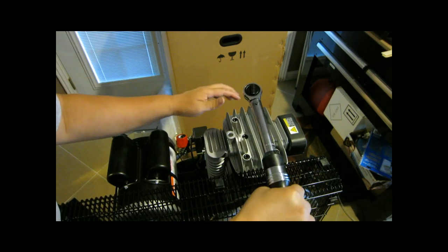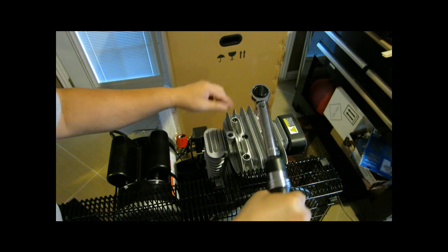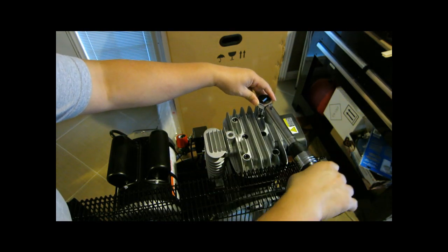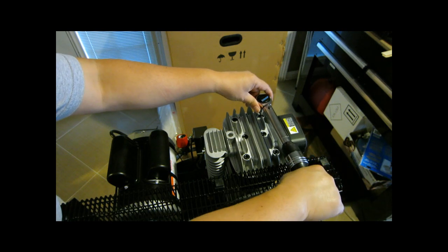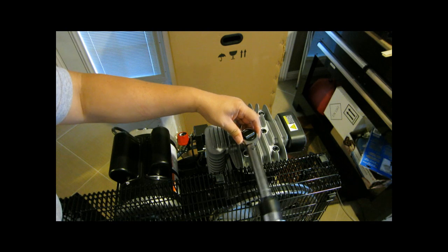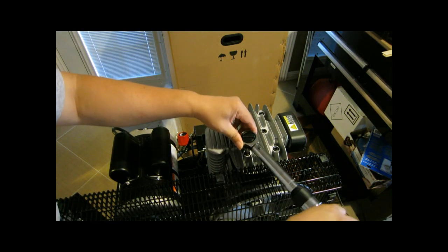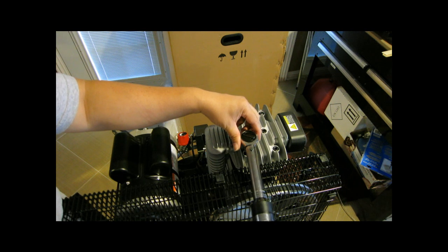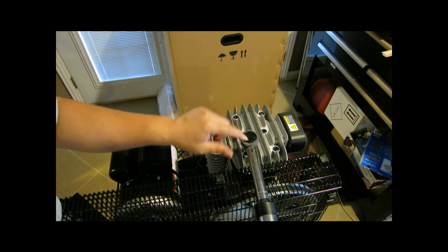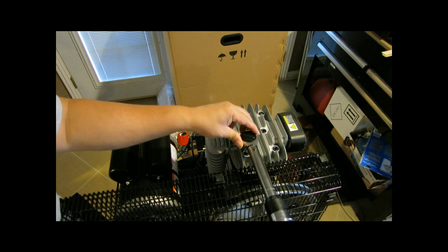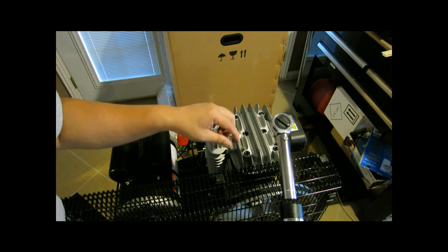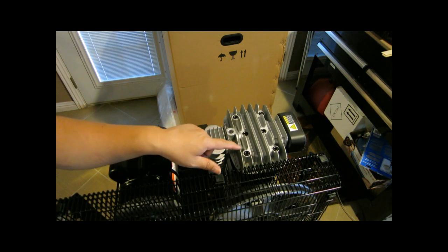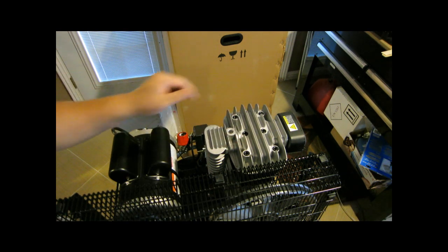Okay this one is loose. It moved a little bit, I shouldn't say loose but it was not at 22 Nm. This one moved a bit. This one which is my lower right was the most loose. So the center ones were tight. This one was the most loose, this one is the second and this is the third.